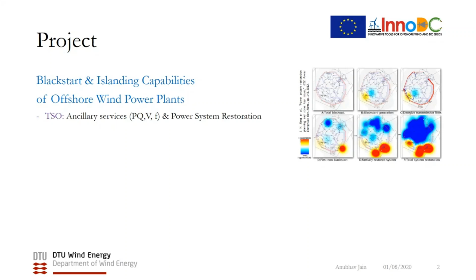This is because traditionally wind turbines are controlled as grid following units, which means they require an external grid voltage point to connect to. Right after a blackout, the network might not be stable enough, and thus early connection of wind power plants can lead to a recurrence of a blackout.